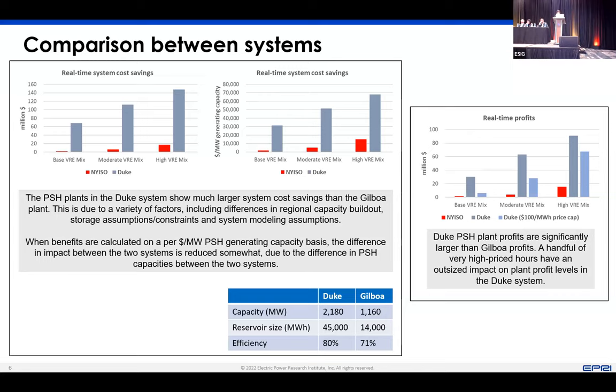And then the right-hand graph you see is real-time profits. You can see, again, the Duke pump storage plant profits are significantly larger. But what we noticed was a handful of very high-priced hours where there were violations that had a really outsized impact on plant profit levels. So we calculated what those profits would have looked like if we had had a $100 per megawatt hour price cap. And they did get reduced fairly substantially there, especially if you look at the base and moderate VRE mix, they're a lot more comparable to the NYISO system.